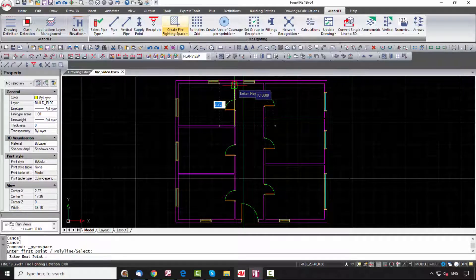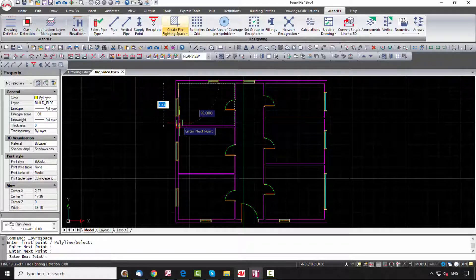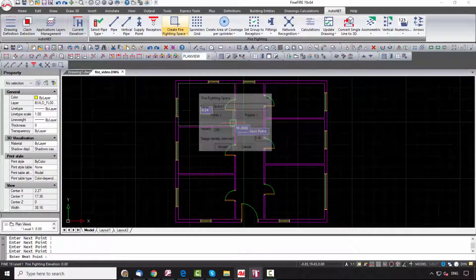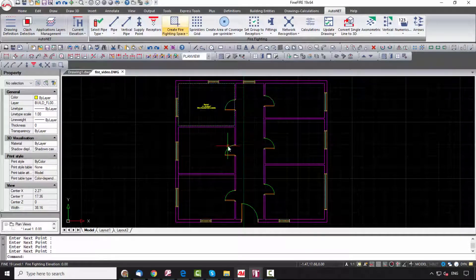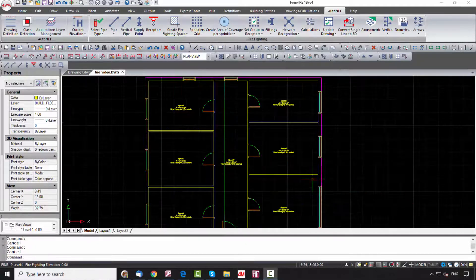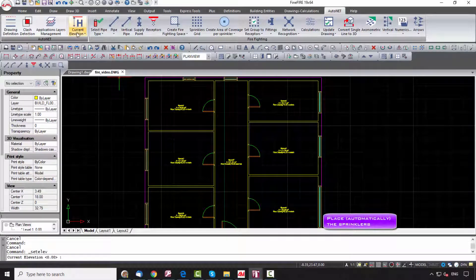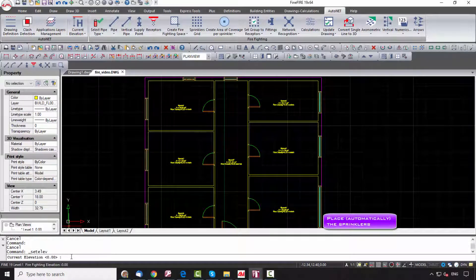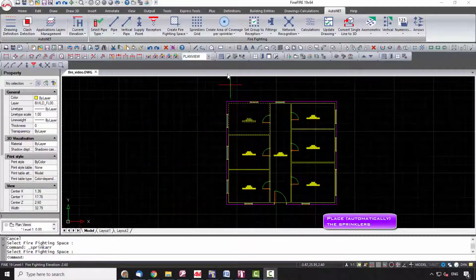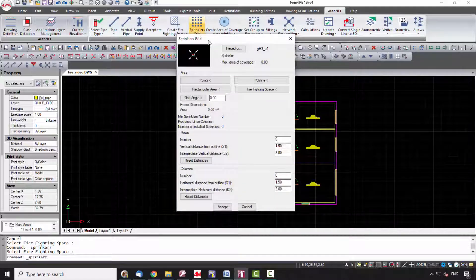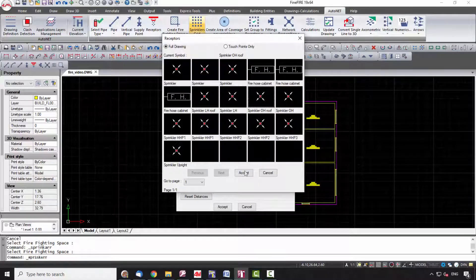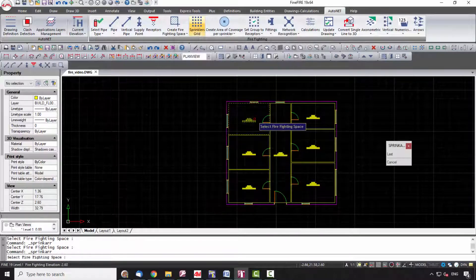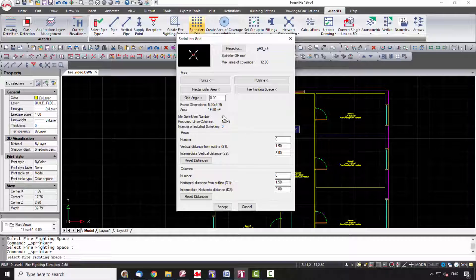The space can be defined either by points or by polyline. Repeat the same steps for every space. Set the elevation where the sprinklers will be. The next step is to place the receptors through the Sprinklers Grid command. In this window, select from the library the type of receptor, and automatically the maximum area of coverage will appear. Insert the number of rows and columns as you wish the installation in this certain space to be, and press Accept.